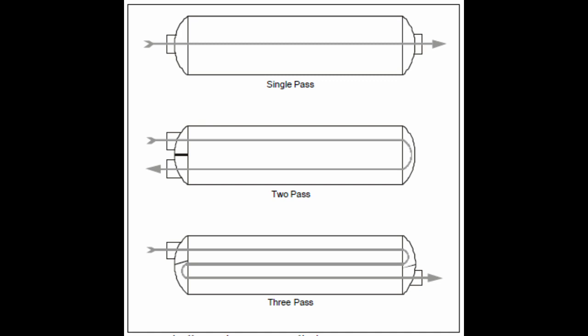In contrast, a two pass heat exchanger, also known as a double pass heat exchanger, has the fluid flow through the tube twice before exiting. The fluid enters the heat exchanger at one end and flows through one set of tubes before turning around and flowing back through another set of tubes in the opposite direction.